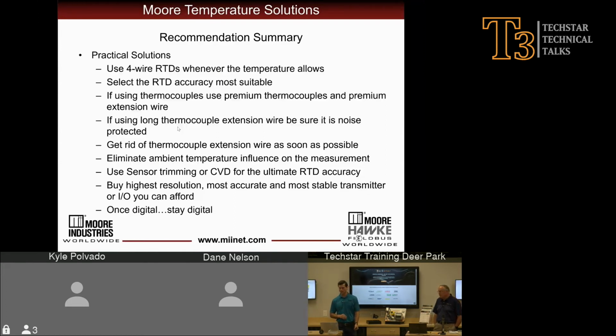Buying the highest resolution, most accurate, and most stable temperature transmitter or I/O that you can afford. Again, this affects the calibrations that you might have to do, the amount of resolution you're able to see, and the changes in your temperature sensor. All of these things affect the operating expenses of that temperature point, as well as the measurement accuracy. And then finally, once you go digital, stay digital. Reduce the amount of error that's introduced into our temperature measurement by going from analog to digital and digital back to analog.